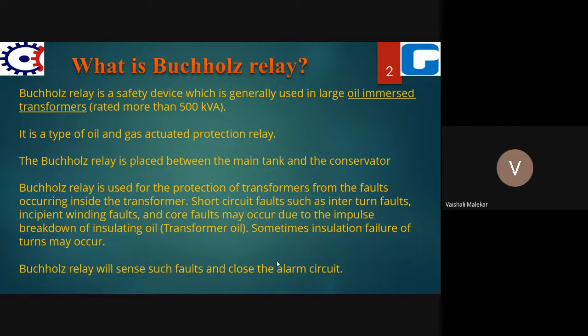It is a safety device which is generally used in large oil immersed transformers, and these oil immersed transformers are of high rating, above 500 kVA. Means this Buchholz relay is used in transformers rated more than 500 kVA. For transformers rated less than 500 kVA, this relay will not be used because it will not be economical. So it is used in oil immersed transformers having a rating above 500 kVA.